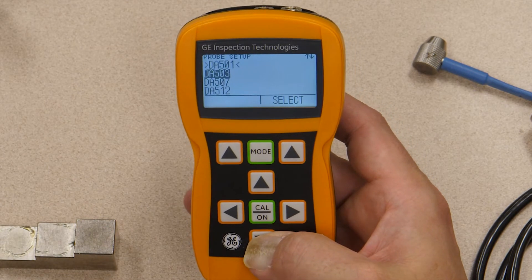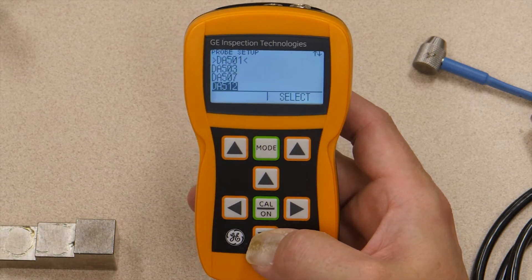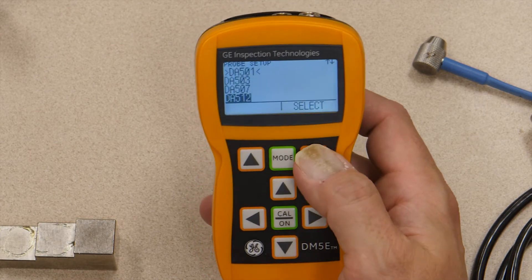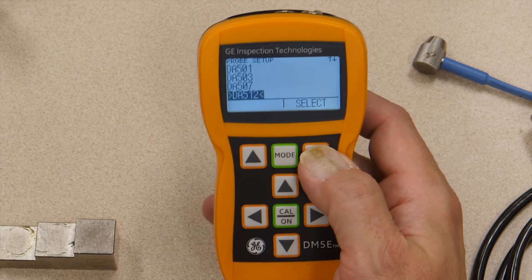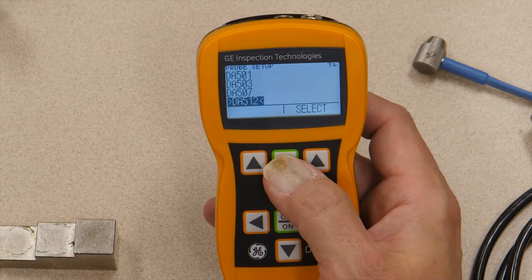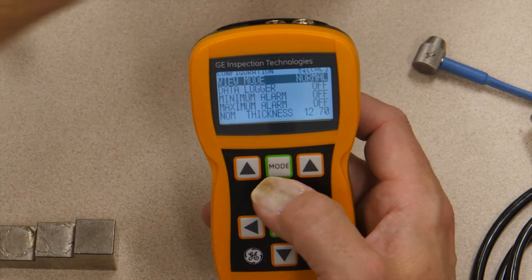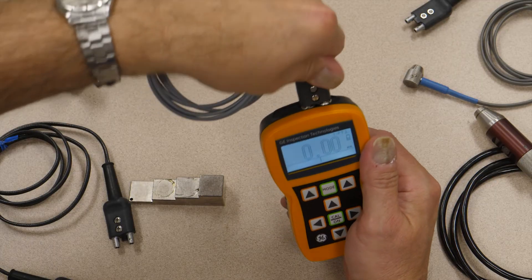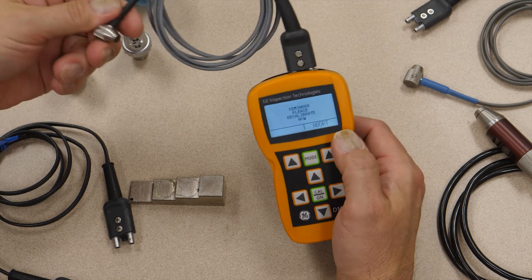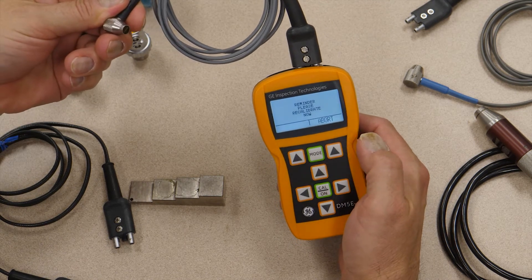So if I were going to use the DA512 probe, for instance, I would scroll down to DA512, press the soft key under select, and now you notice the greater than, less than symbols are down to the DA512. So with that, I can go back to my measurement menu, plug in my DA512 probe, and the first thing it tells me is I need to calibrate.